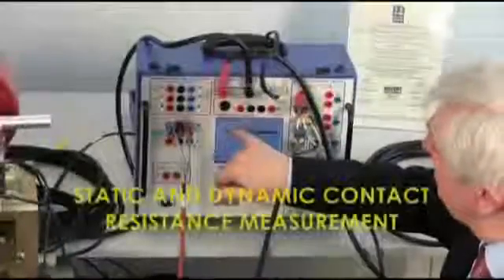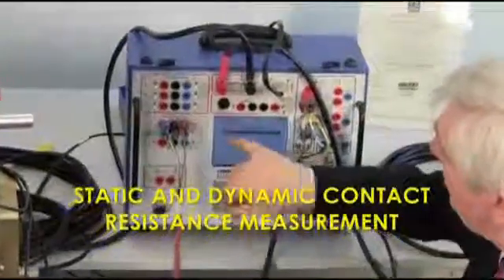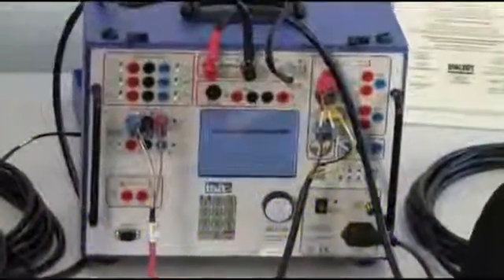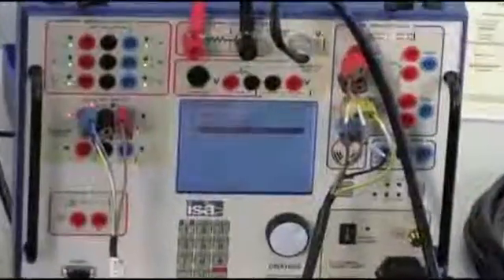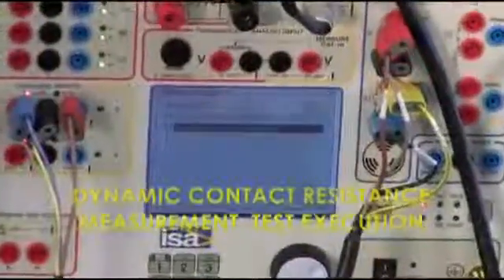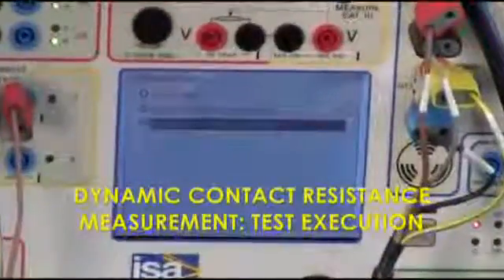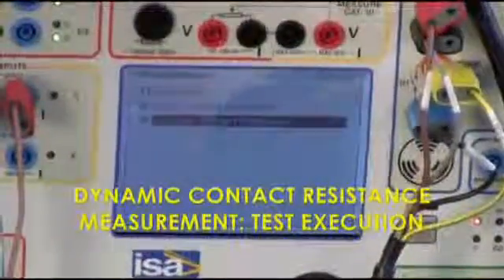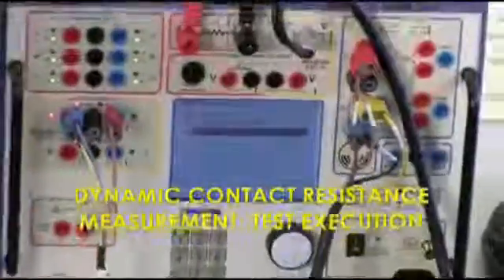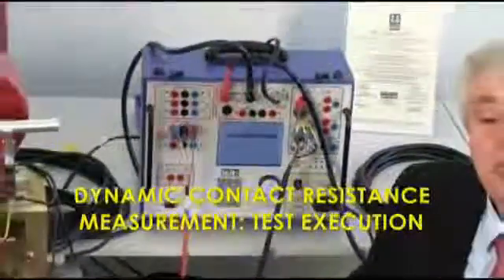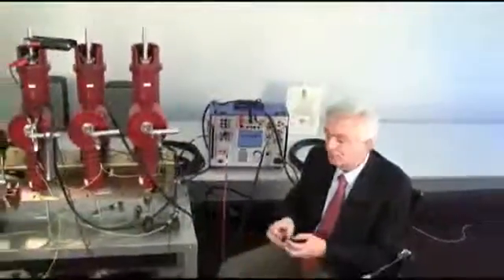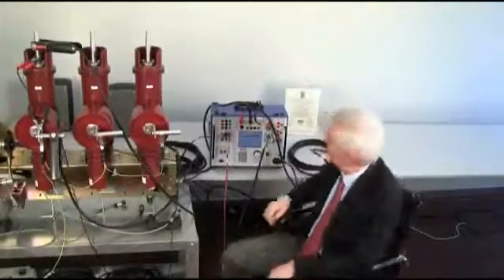You see, you have static contact resistance, but you also have dynamic contact resistance. What is it? It is the possibility that we have to measure the resistance while the contact is opening. And this can be very, very important. We have had one instance of a circuit breaker on a ship that had loose nuts, and because of that, the contact was absolutely unstable during the opening and closing. And this could be seen by the dynamic resistance measurement.